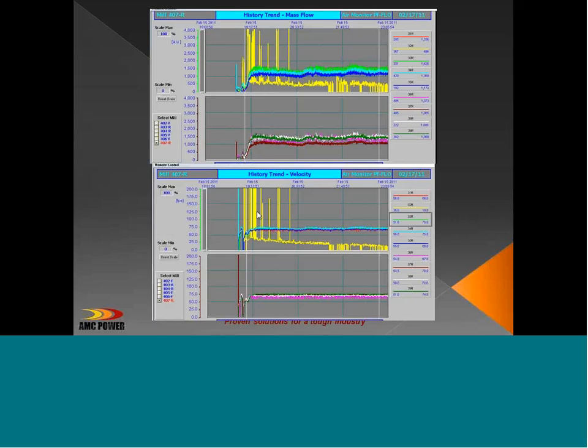And if we look at the velocity screen, we can see that the velocity was well below minimum transport velocity. You know, at below 50 feet per second, you're not going to transport fuel. You're just throwing it into that pipe, and it's going to sit there. And so what happened was they were filling the pipe with coal, and it eventually caught fire.